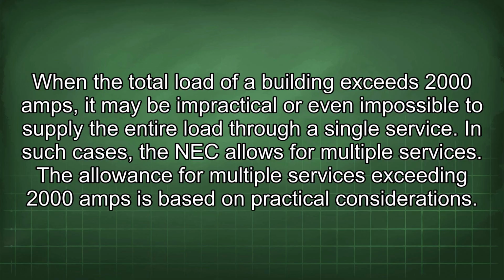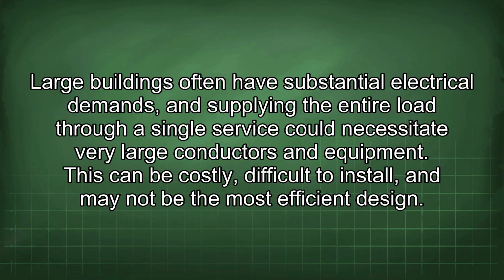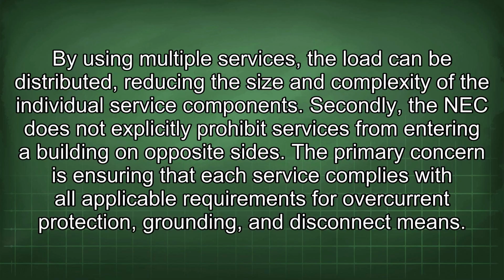The allowance for multiple services exceeding 2000 amps is based on practical considerations. Large buildings often have substantial electrical demands, and supplying the entire load through a single service could necessitate very large conductors and equipment. This can be costly, difficult to install, and may not be the most efficient design. By using multiple services, the load can be distributed, reducing the size and complexity of the individual service components.